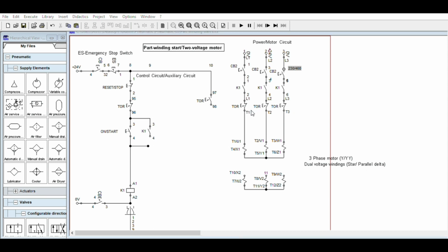Let's say we're using the one voltage here. It's 230 only, but energize the half winding first, then energize the two windings together in parallel. We need how many contactors to do this one? This one is one contactor. This one is another contactor. But we need to switch off later. So this is the first contactor, K1. And later we'll connect this one.